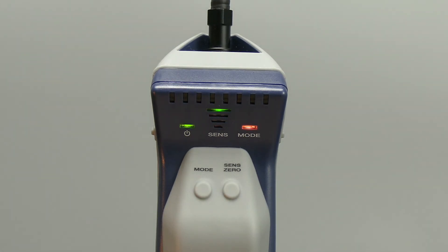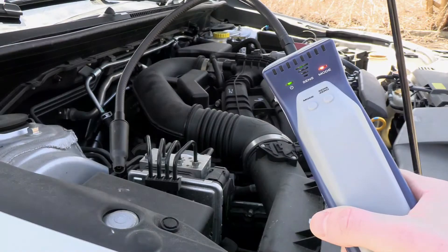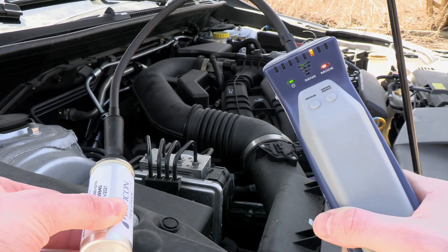In pinpoint mode AST 200 IR will automatically zero to the refrigerant background after alarming for a short time allowing you to easily locate higher levels of refrigerant.